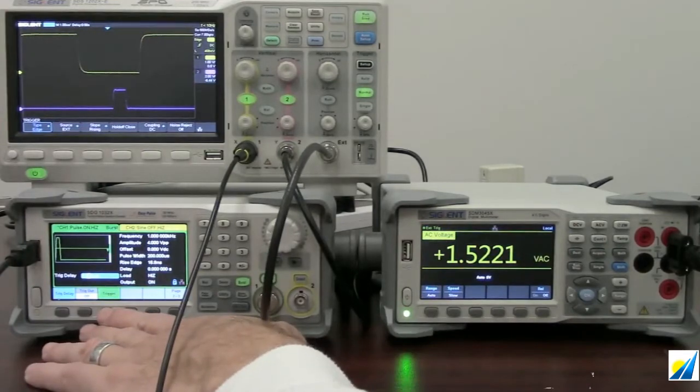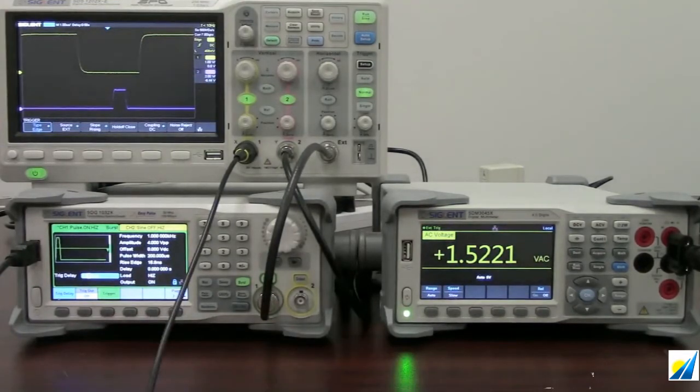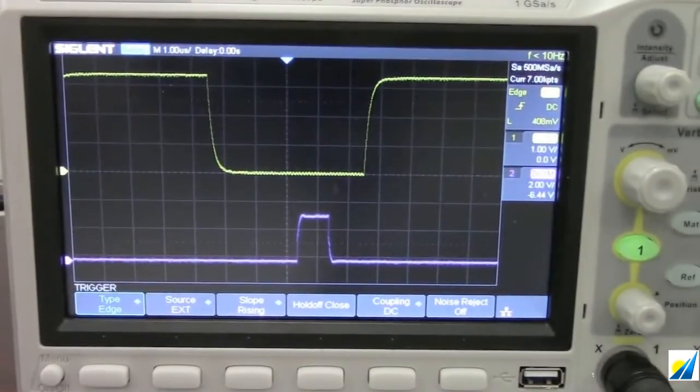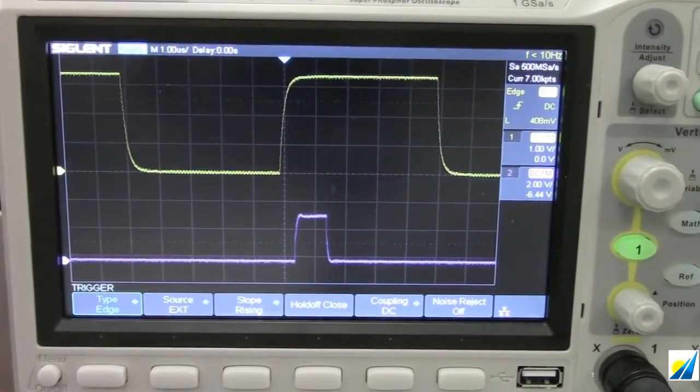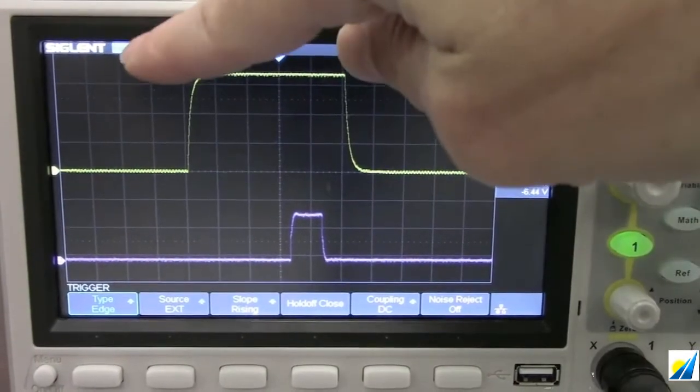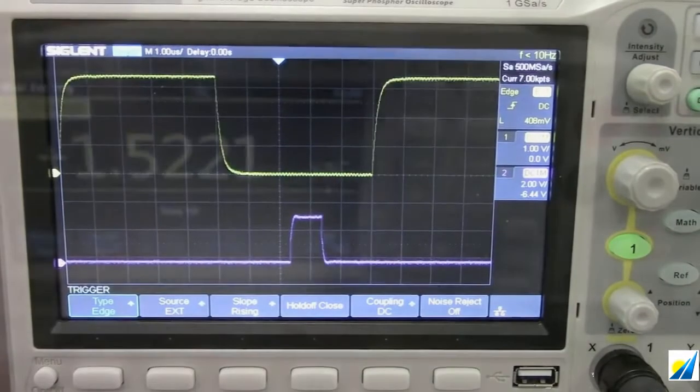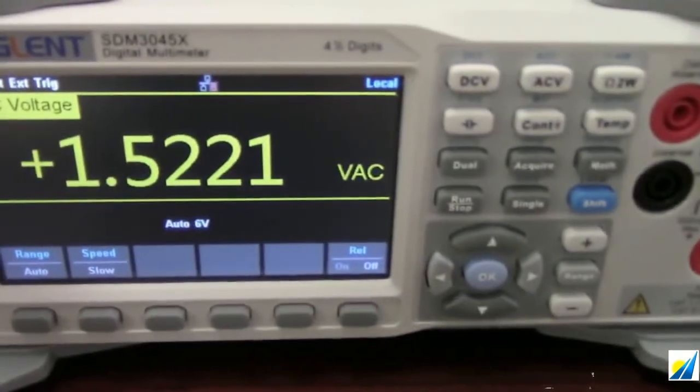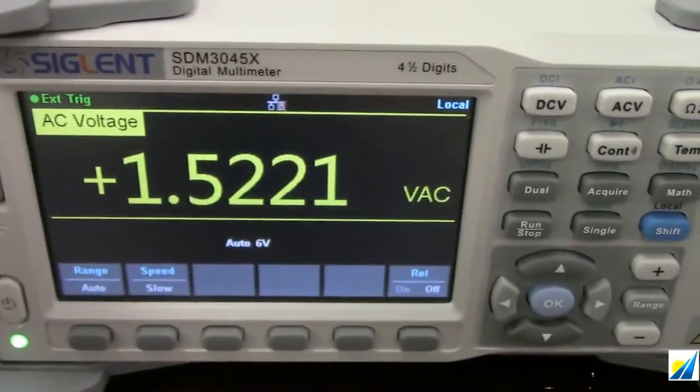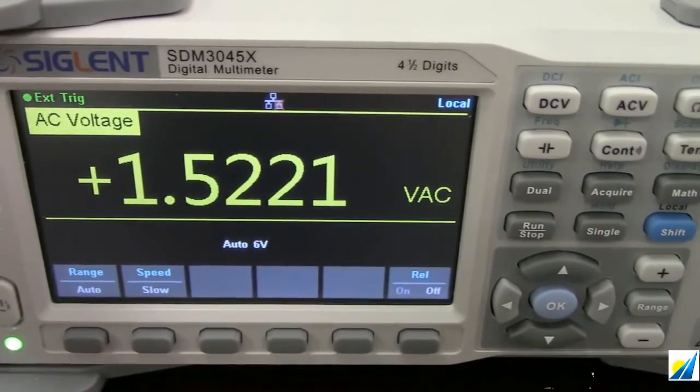But I'll perform that again. Pressing the trigger button, you'll see we actually get external trigger here. And you can see that indicated by the trigger indication up at the top of the screen here on the scope. And as we go over to the multimeter, you can also see that we are getting its external trigger. So it is also triggering and making a measurement.